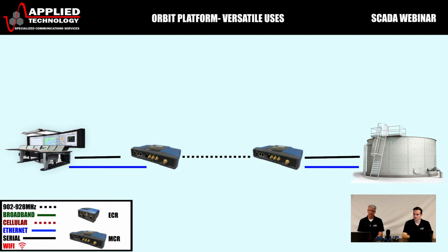One note on that is signal strength and performance needs to be in place. In the 900 license and 450 license, Ethernet is traffic it can handle, but it's not to be considered high-speed Ethernet, meaning you're not going to connect a computer to another computer through this setup. This is a slow process Ethernet, and the SCADA system must be designed with that mindset. It needs to do a poll and response format so it has time to respond to each poll.